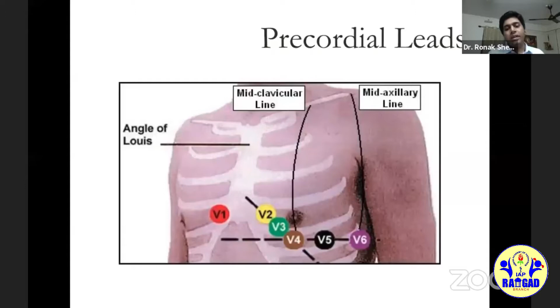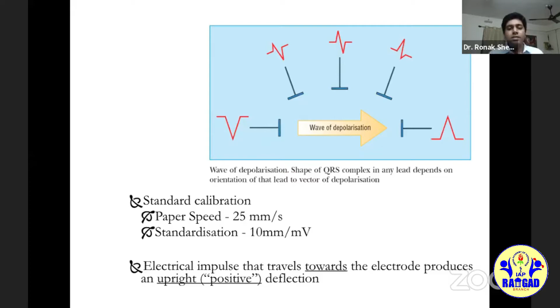So then coming to the standard ECG recording, or the standard calibration of the ECG machine. The ECG paper in the standard format is designed to move at a speed of 25 millimeters per second, and it is programmed to have a 10 millimeter deflection for every millivolt of voltage that it detects. So for 1 millivolt, it will have a 10 millimeter deflection. This is the standard calibration. We'll come to some examples where we need to change these calibration settings.